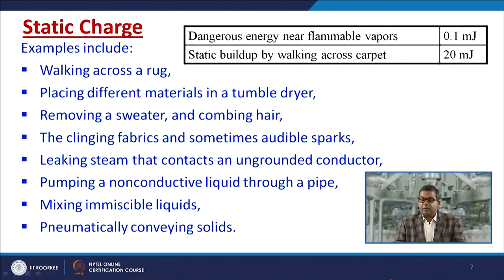The dangerous energy threshold near flammable vapours is around 0.1 millijoule. Simply walking across a carpet can generate around 20 millijoules of static charge — illustrating how serious the hazard is. It is therefore a primary requirement to remove any excess static charge built up on a surface to avoid fire and explosion hazards.